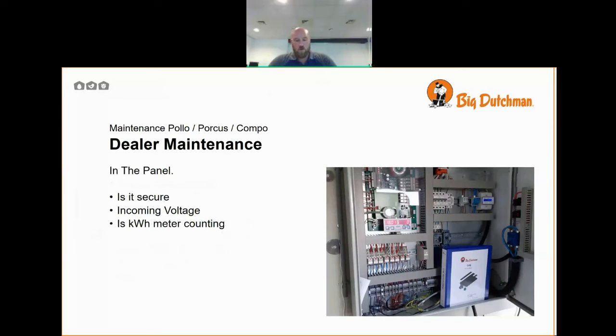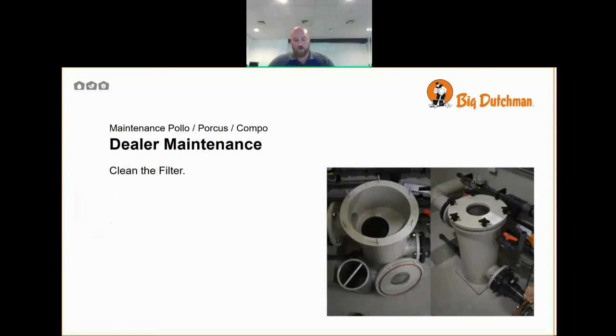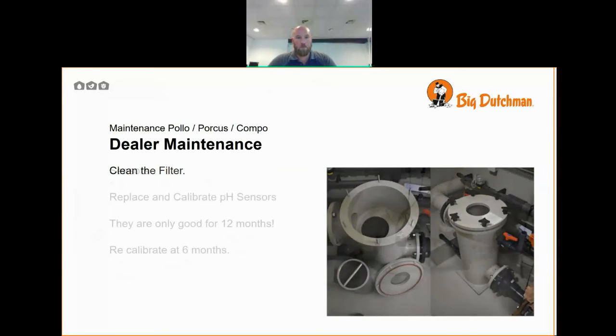In the panel, we need to make sure that the panel is secure and all of the components are secure, the connections are secure. Is the incoming voltage correct? This is also worth recording. And is the kilowatt hour meter recording correctly? Clean the filter, as previously discussed in user maintenance.